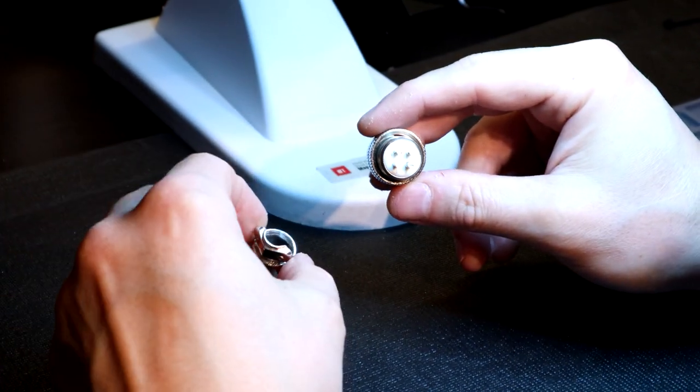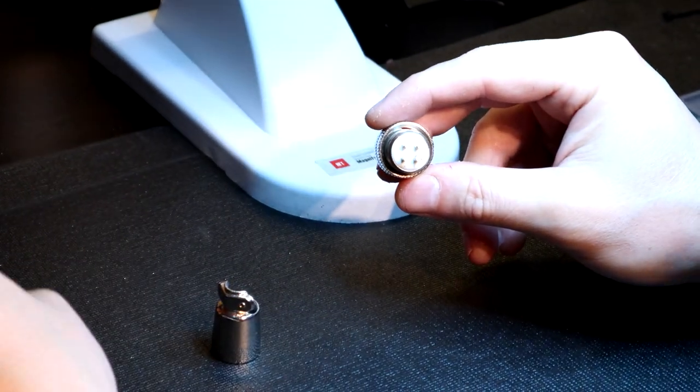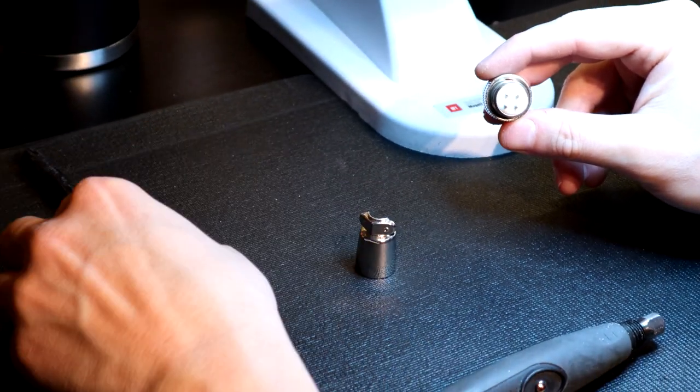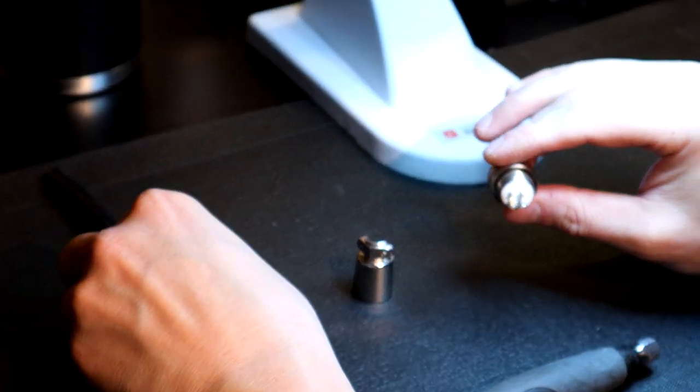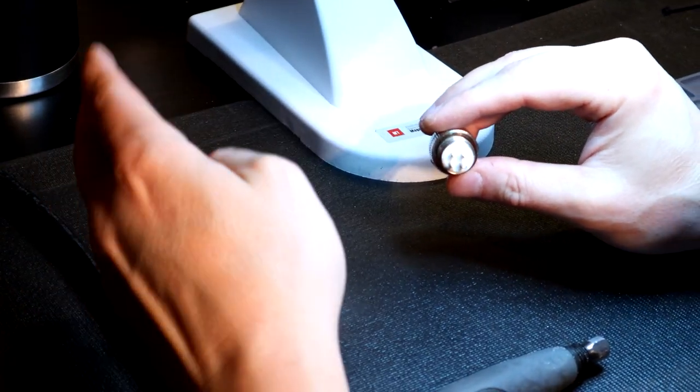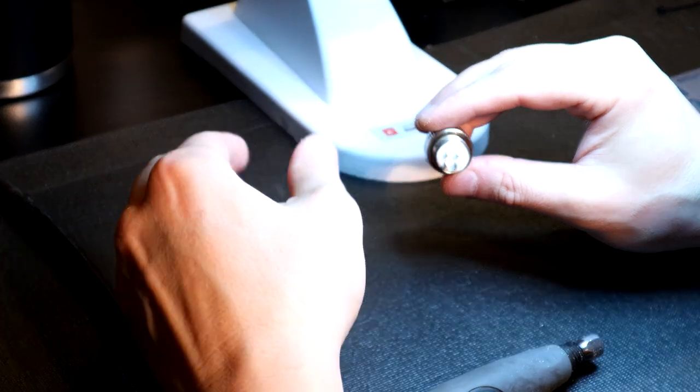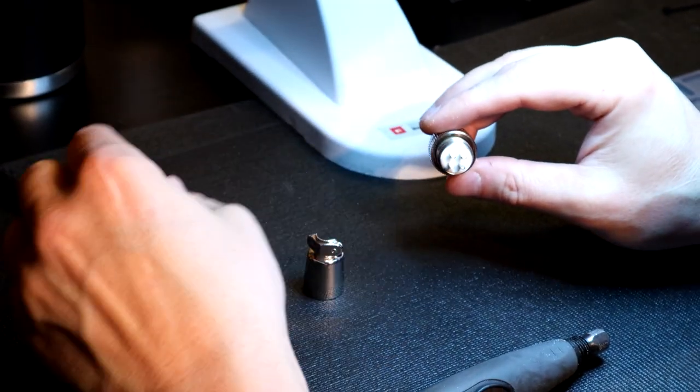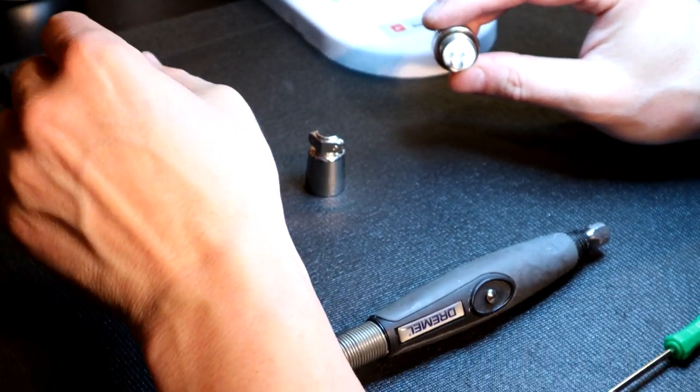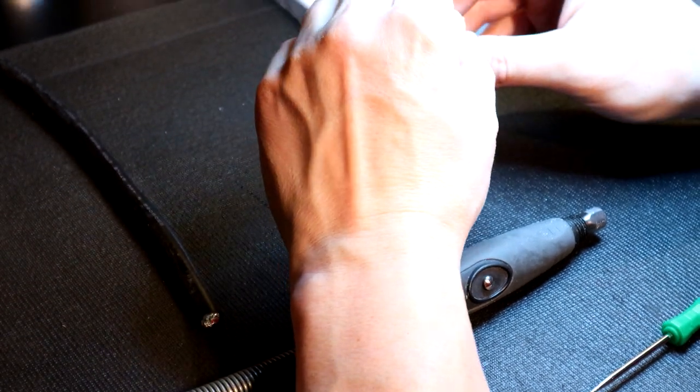And double shielding is imperative, because we want to use double shielded cables, so we mitigate both EMI frequencies. There's a high and a low frequency. And with double shielding, you've got the mylar foil and the tin-braided copper, which mitigates both.